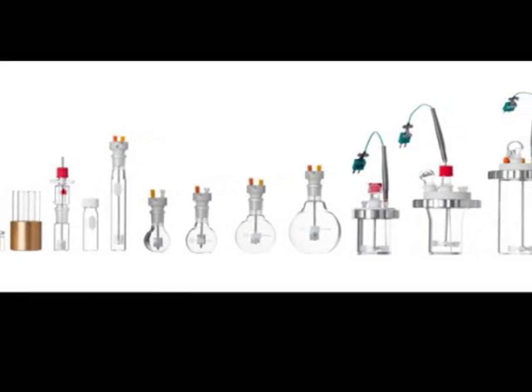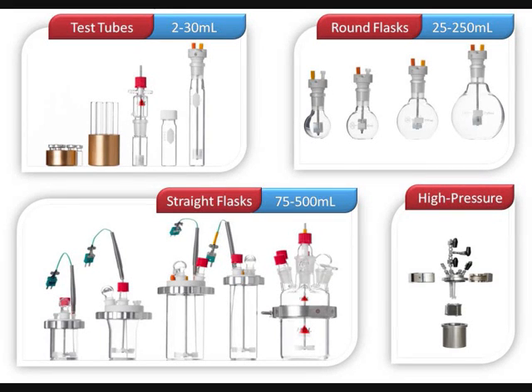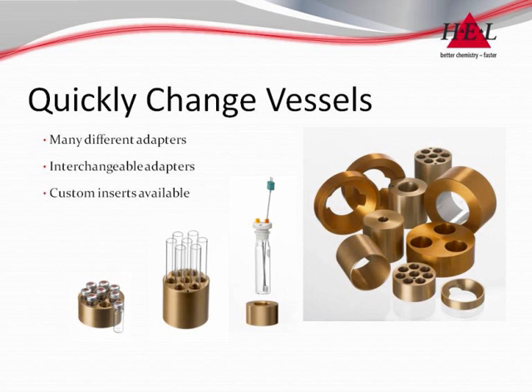Both systems accept a wide range of vessel sizes and architectures, from 2 mL HPLC vials, up to 125 mL on the PB-8 and to 500 mL on the PB-4. Vessel types and sizes are changed within seconds with simple drop-in inserts.